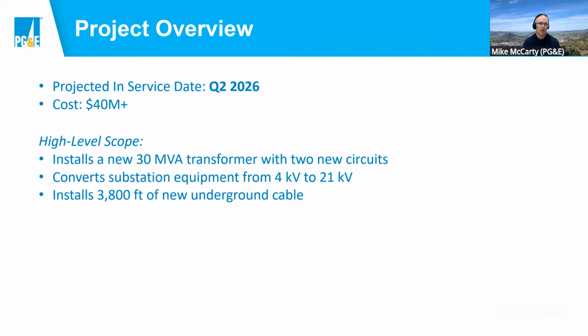But anyways, just to summarize: new 30 MVA transformer, we're converting voltage from 4 kV to 21 kV on our distribution system. And lastly, we are installing some additional cable as a part of this project to bring that 21 kV out into the other areas that are currently on that 21 kilovolt system to allow us to increase capacity and decrease outage exposure.